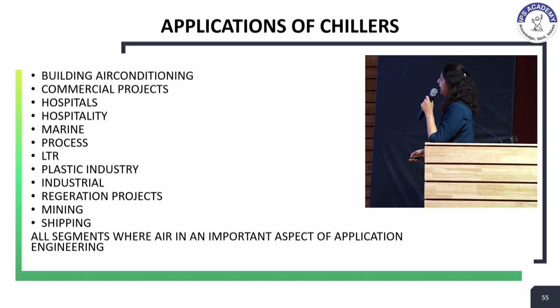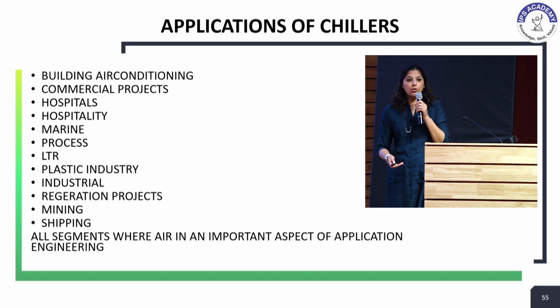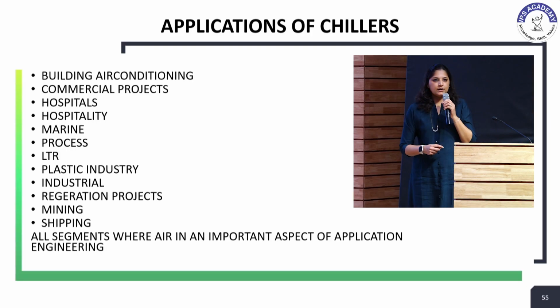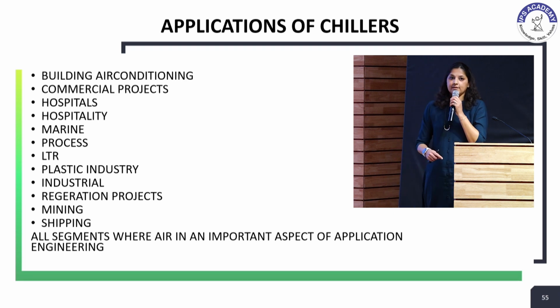So chillers are usually applied to building air conditioning, commercial projects, hospitals, hospitality, marine, process, low temperature, plastic industry, industrial applications, then mining, shipping. So wherever there is a requirement of chilled water or chilled air, chillers are applied to all those applications. Now chillers can be applied to a comfort application like air conditioning, which you are experiencing here, or they're also applied in industrial applications where chilled refrigerant is required at -50 temperature as well.